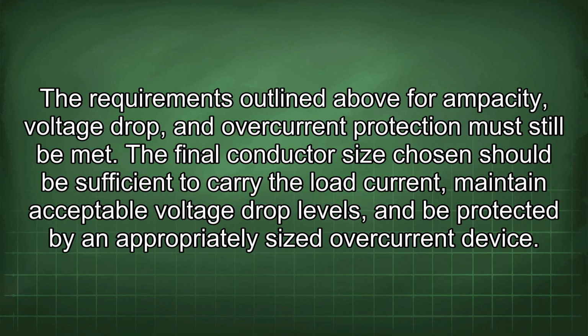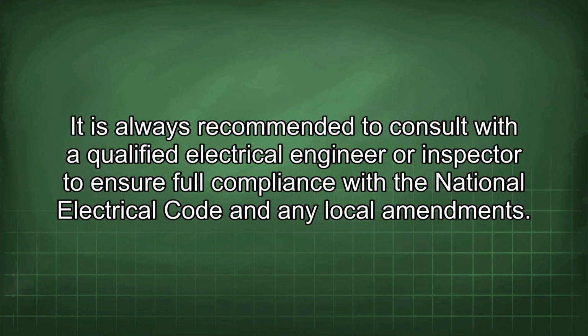The requirements outlined above for ampacity, voltage drop, and overcurrent protection must still be met. The final conductor size chosen should be sufficient to carry the load current, maintain acceptable voltage drop levels, and be protected by an appropriately sized overcurrent device. It is always recommended to consult with a qualified electrical engineer or inspector to ensure full compliance with the National Electrical Code and any local amendments.